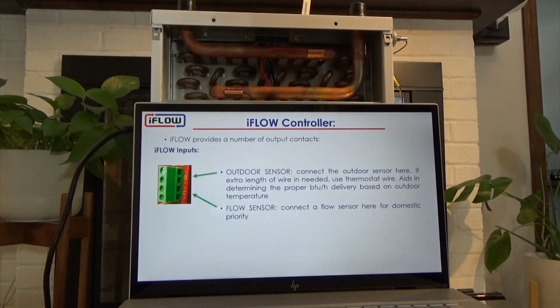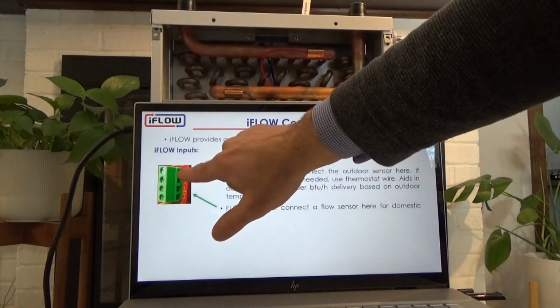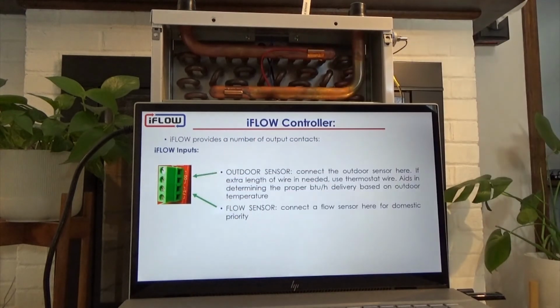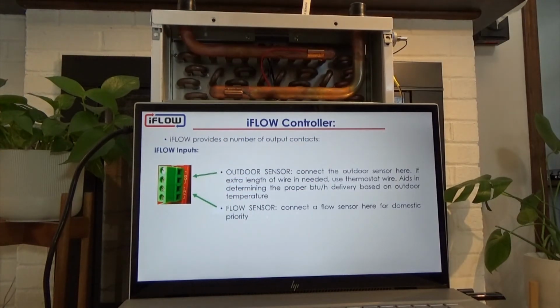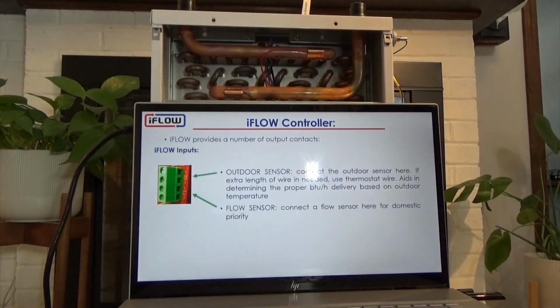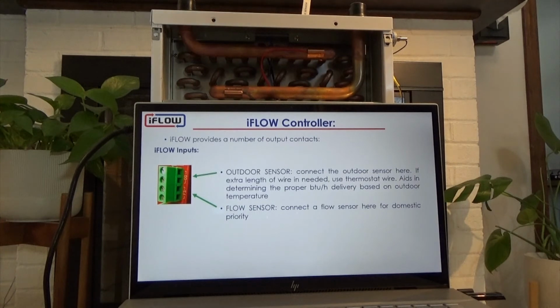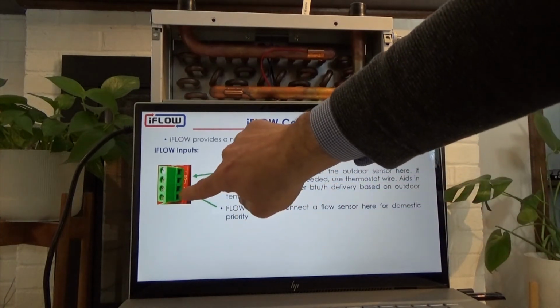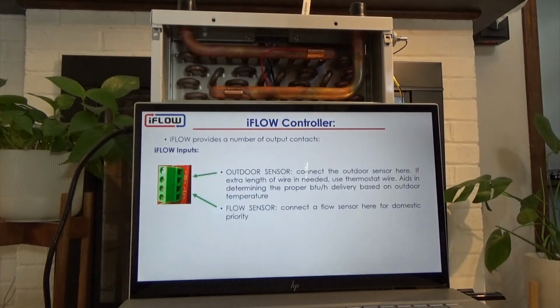The outdoor sensor connects to the upper right side on this board in a contact called OD for outdoor. It could also be OTS for outdoor temperature sensor. So there are a couple of different acronyms that we've used. And then below that you have the flow sensor. And the flow sensor connects and just gives us domestic priority. So if you want domestic priority and you're installing a flow switch, it would connect to those two contacts.